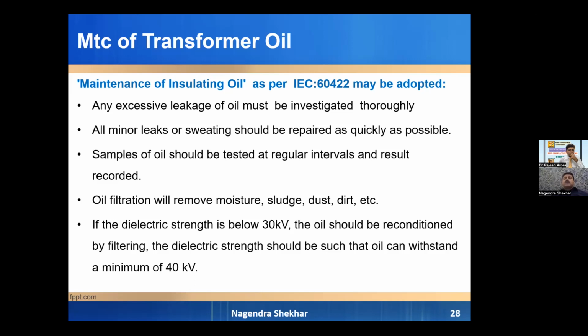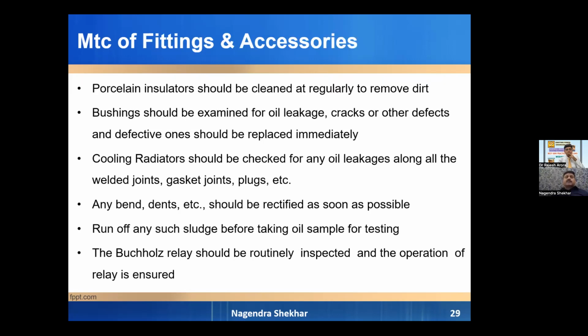For that, we can use an oil filtration machine on site, or if the results are very poor and overhauling of the transformer is required, we have to send the transformer to the workshop, so that the winding of the transformer is taken out, properly cleaned, repaired, dehydrated, and new or dehydrated transformer oil fitted. So basically it is revitalizing the transformer. The fittings and accessories of the transformer should be cleaned properly, bushings should be examined, and cooling radiators should be examined and kept clean so that air can flow across the radiators. If there is any bend or any leakage, that has to be rectified.